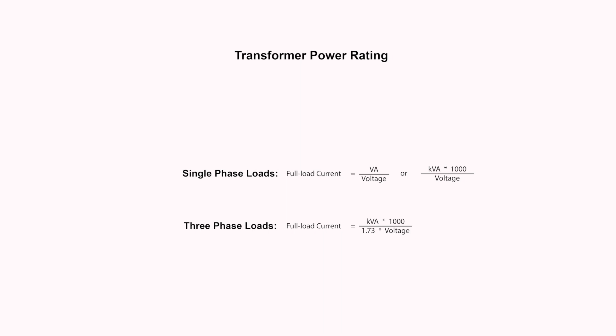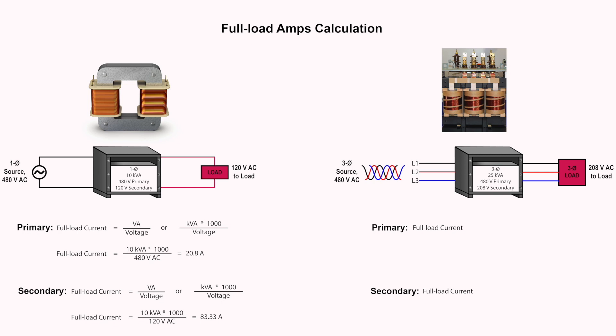Let's look at some examples of how full load currents are calculated. Here we have a single phase 10 kilovolt amp transformer rated 480 volts primary and 120 volts secondary. With the information given and using the full load current equation, the primary and secondary full load current are calculated as follows.